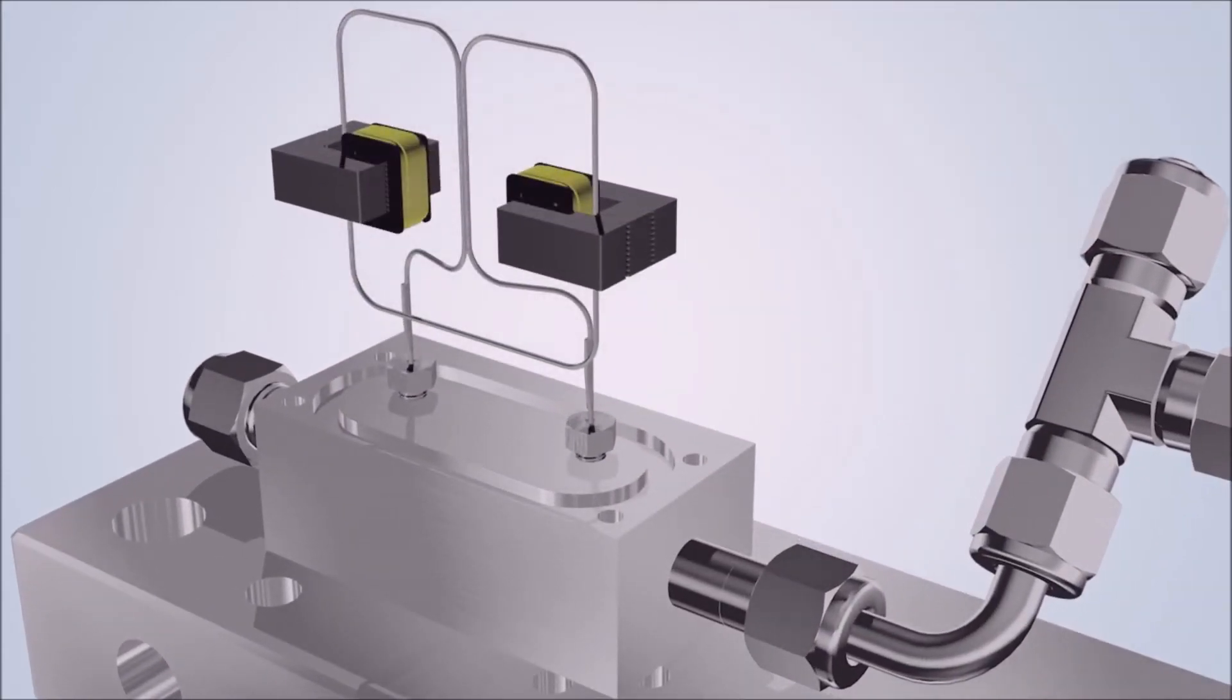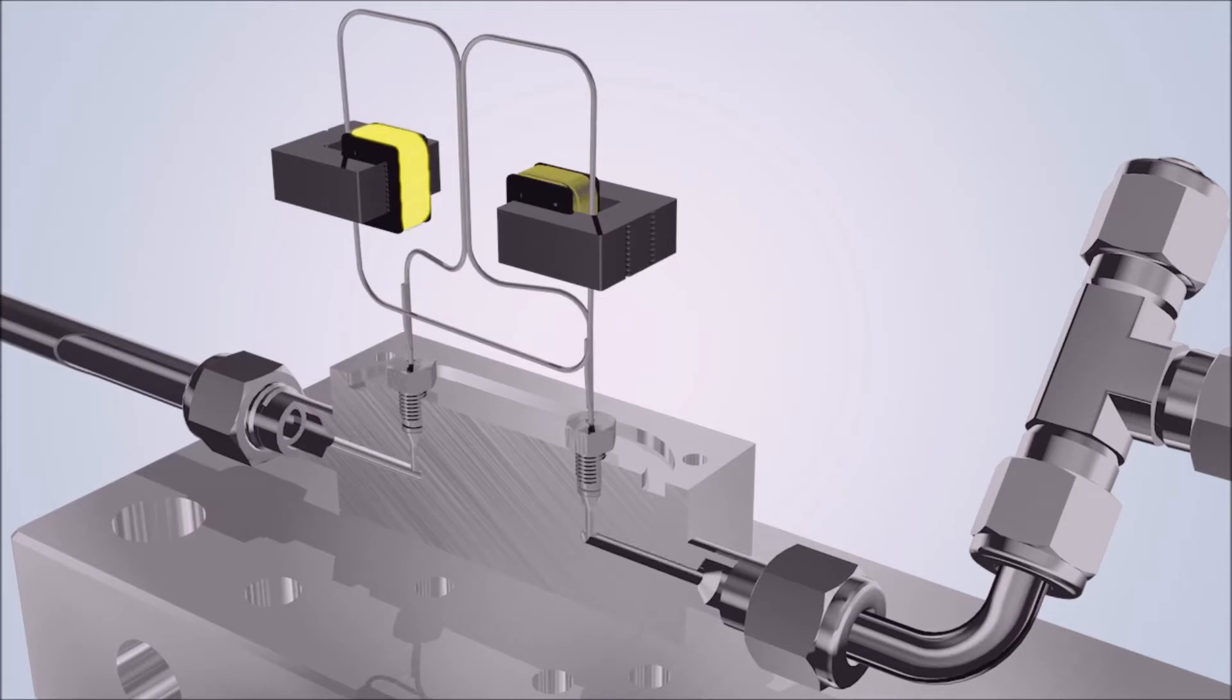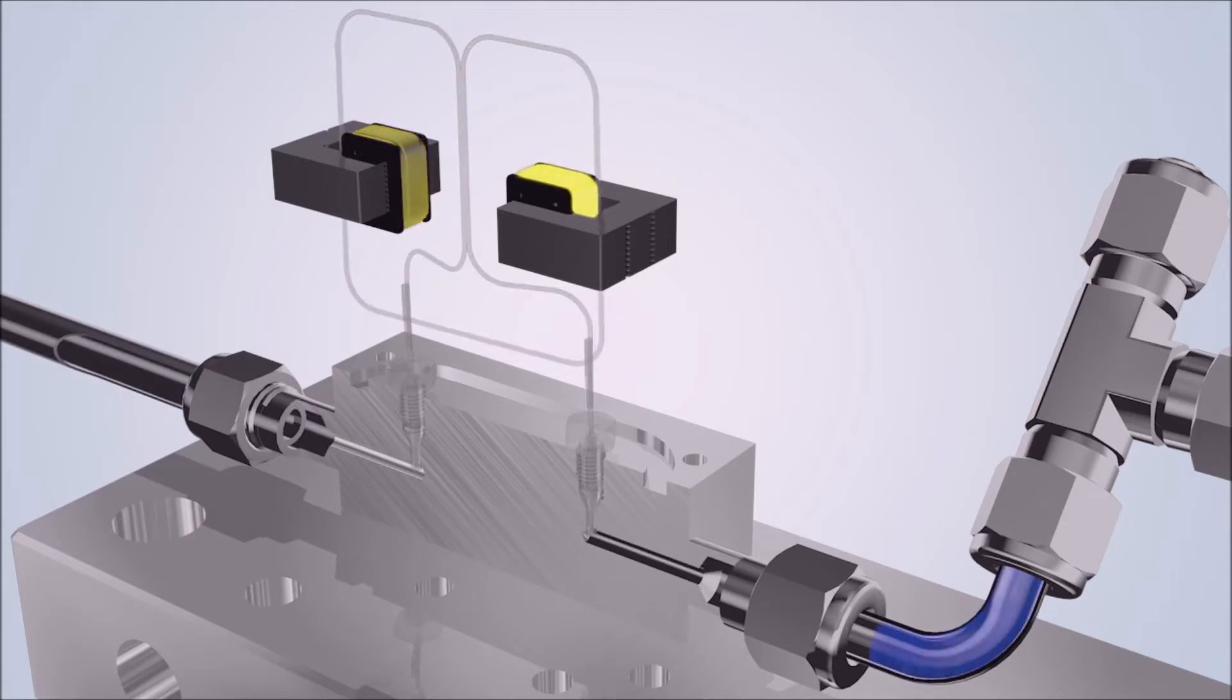Once the power source is connected, the sensor tube immediately begins to vibrate. This vibration, which has been slowed down considerably in the video, is generated by energizing two actuators alternately, thereby creating a magnetic field.